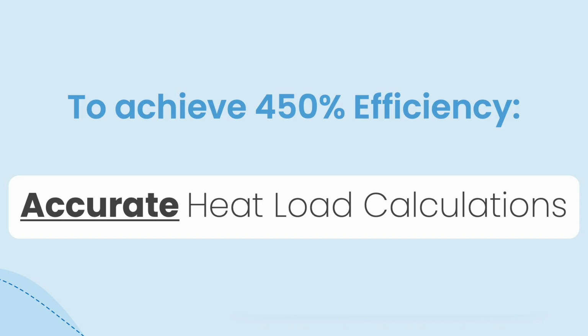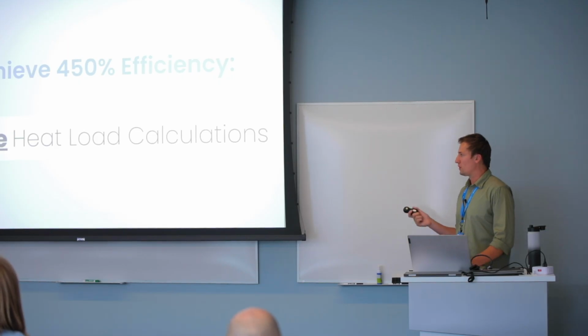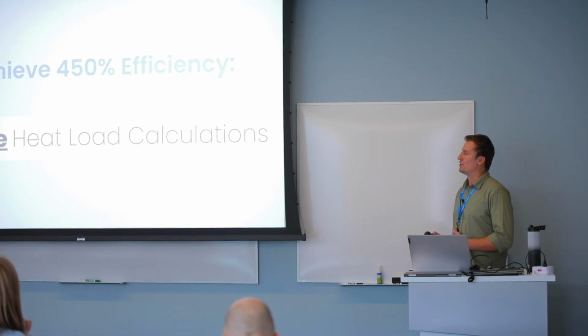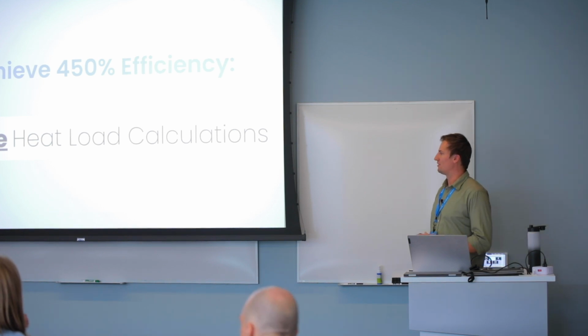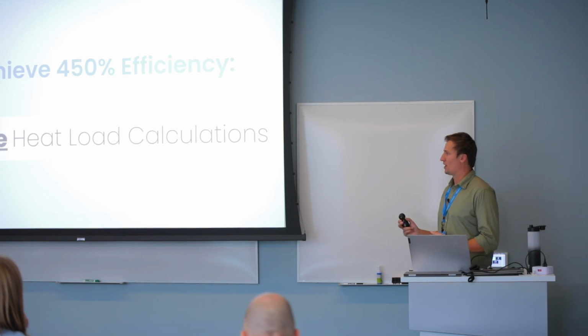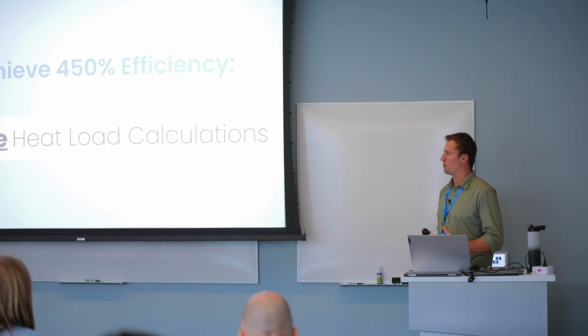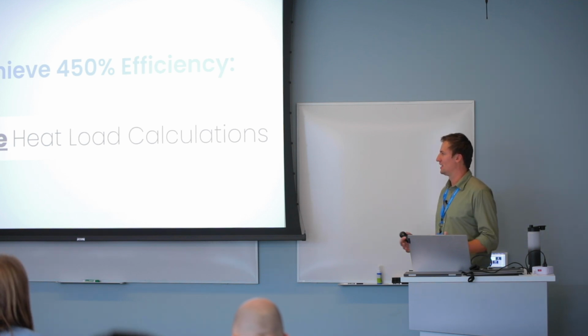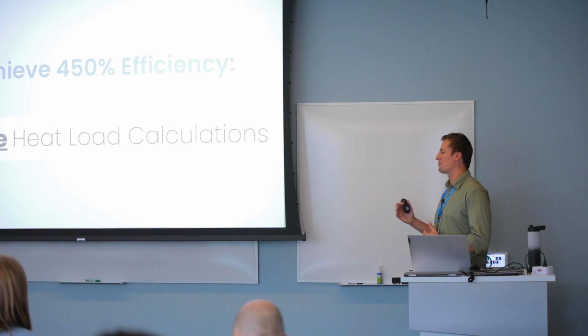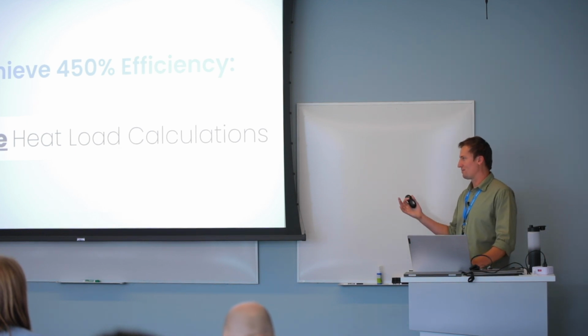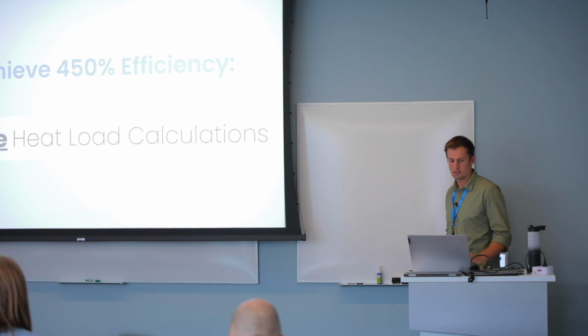So it might be quite surprising to hear, but to achieve this level of efficiency, it's quite straightforward, and it just comes down to something you're already doing. You've probably heard it time and time again the last couple of days, but it all comes down to your heat load calculations. I bolded and underlined accurate because that is the key here. You can do a quick heat load calculation, but if it's not accurate, the efficiency just falls off a cliff. So if you oversize, use rule of thumb, or be a little bit conservative, it's all just going to be a really low-performing heat pump system. If you oversize enough or undersize enough, it essentially takes you back to the 2022 examples I was seeing, where people hadn't done accurate heat load calculations. So oversizing is just as bad as undersizing when it comes to heat pump installs.